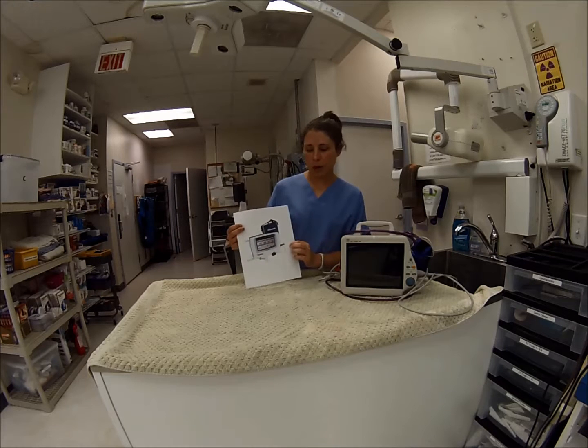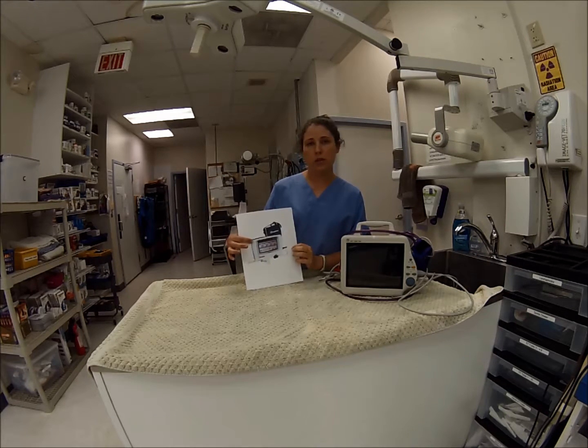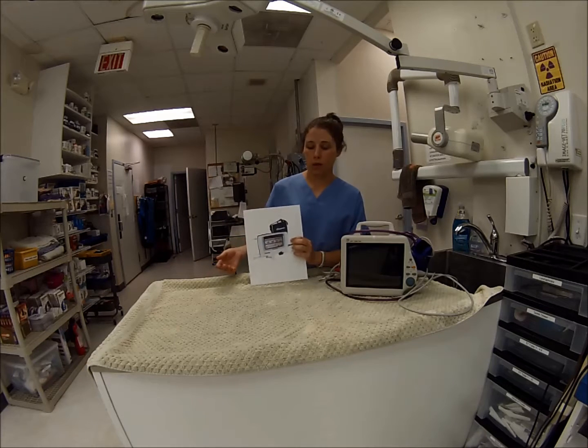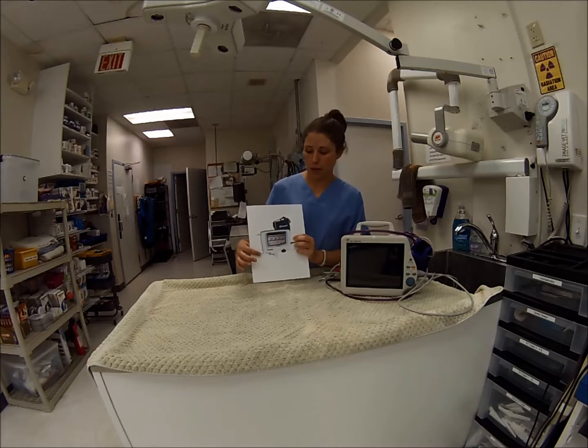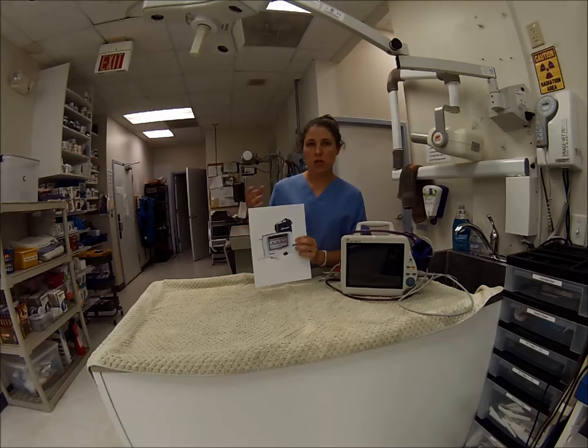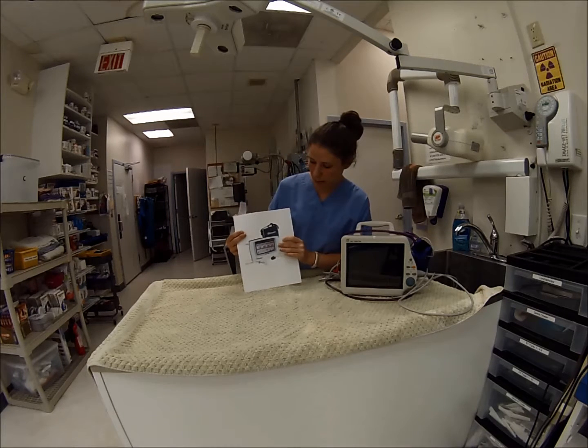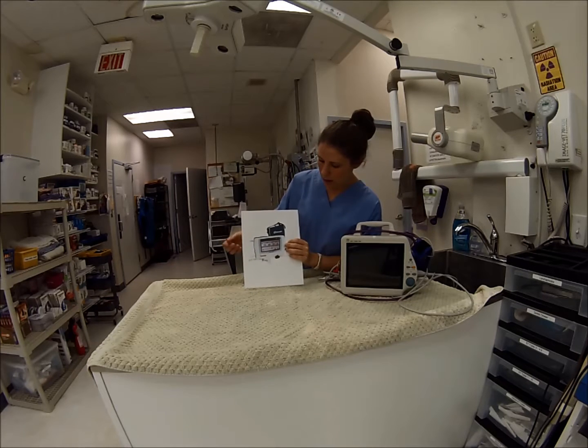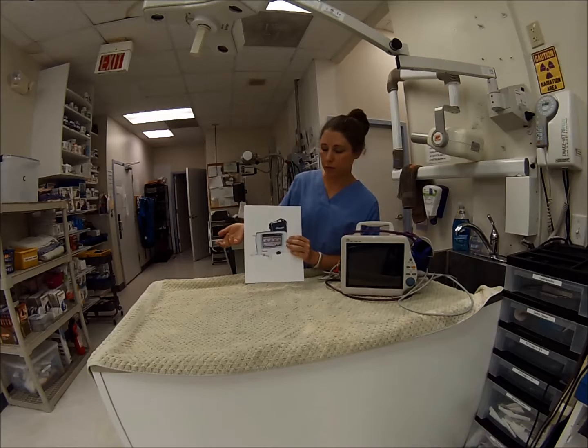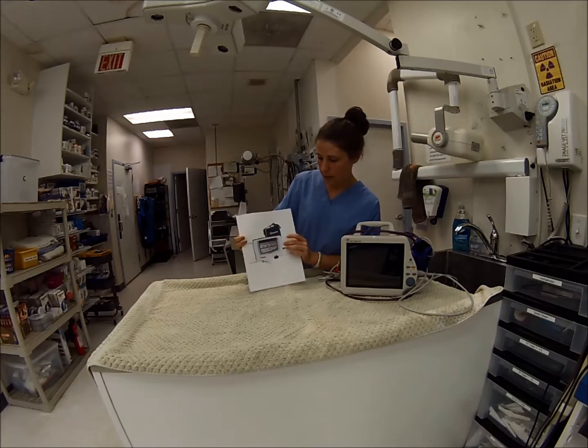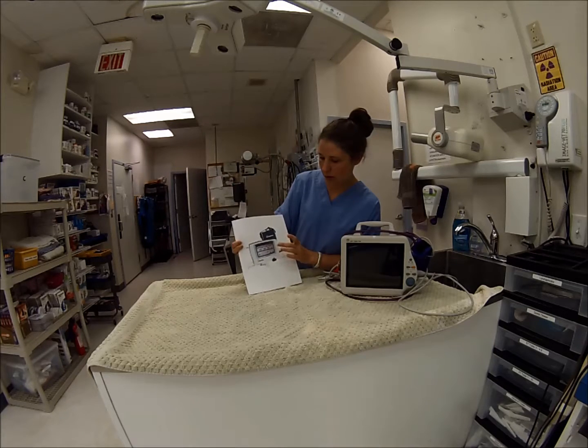In this side stream capnometer, the sensor is actually located within the machine. On mainstream capnometers, the sensor is hooked up directly between the patient's breathing circuit and the endotracheal tube. So as the patient inhales and exhales, readings show up on the capnometer. This one shows a respiratory rate in breaths per minute right here, and it also displays the end tidal CO2 in millimeters of mercury, which is right here. Normal end tidal CO2s are between 35 and 45 millimeters of mercury. This particular capnograph also displays the heart rate as well as the SpO2.